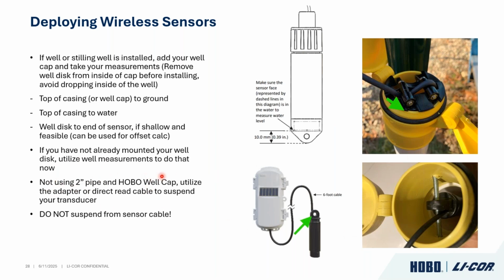If you're not using 2-inch pipe and our well cap, there are other ways to mount this. One thing you don't want to do is suspend the entire setup with this sensor cable, since it's not meant to take tension. You have two options: suspend it from this adapter, which has a little eye hook or eye bolt that you can run a bolt through, or suspend it the same way as the well cap, using the direct read cable, which can take tension. The sensor cable cannot.